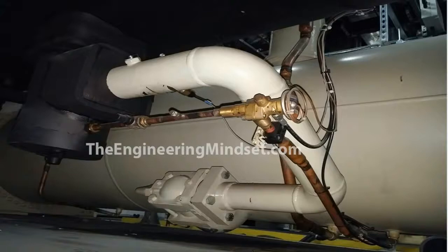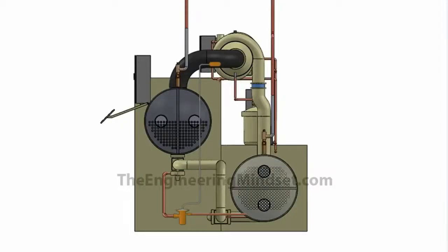Attached to the pilot expansion valve is this capillary tube. This rides up and attaches up into a thermal bulb, which is placed on the suction line of the compressor. So just to give you a side view there of how it's all connected. We've got the pilot valve located down here with the connection going to the condenser, and that flowing through into the base of the main expansion valve.